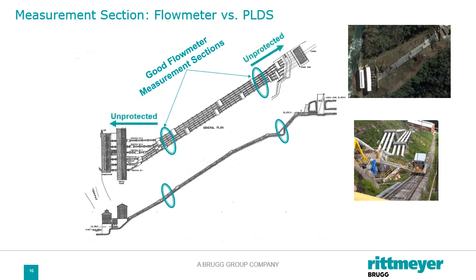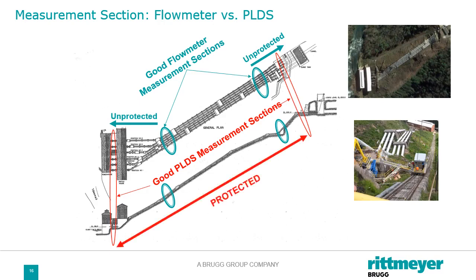The problem is we can only protect what's between the two measurement sections. Everything else remains unprotected, and that's just, in this case, way too much. So we want to push those flow meter sections as far to each end as possible. So then we can get the full coverage. The problem being those aren't necessarily good measurement sections.